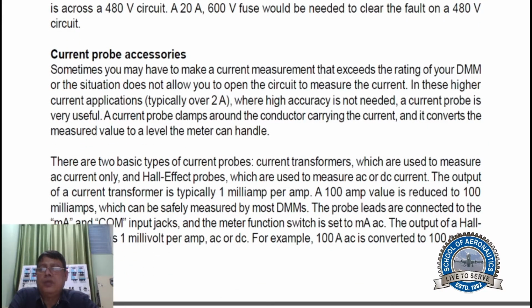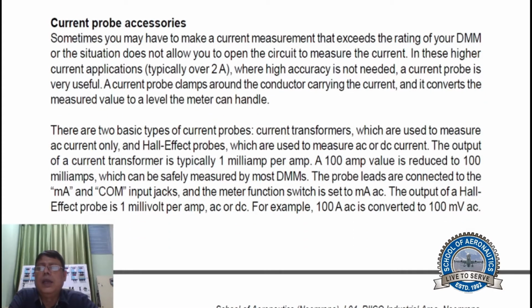Current probe accessories. Sometimes you may have to make current measurements that exceed the ratings of your DMM, or the situation does not allow you to open the circuit to measure the current. In these higher current applications, where high accuracy is not needed, a current probe is very useful. A current probe clamps around the conductor carrying the current, and it converts the measured value to a level the meter can handle. There are two basic types of current probes: current transformers, which are used to measure AC currents only, and Hall effect probes, which are used to measure AC or DC currents.